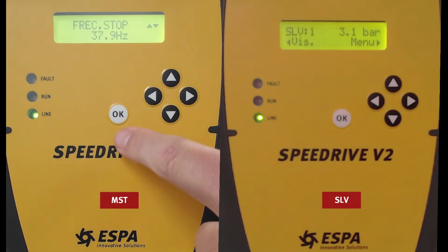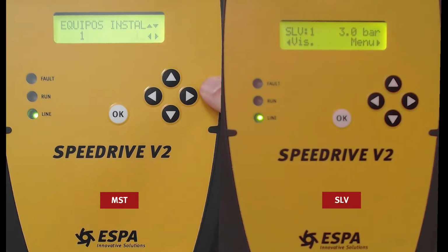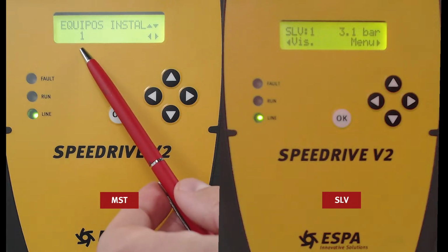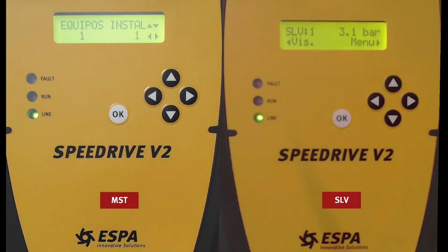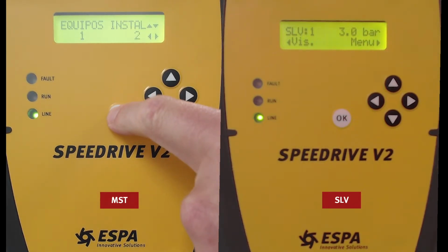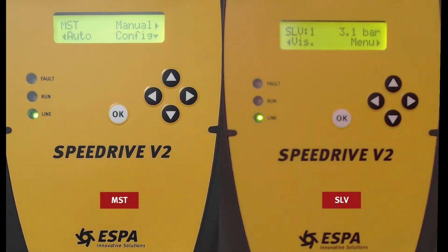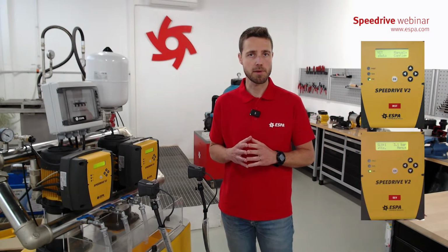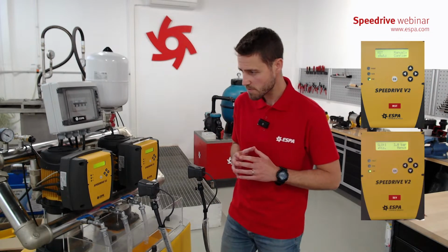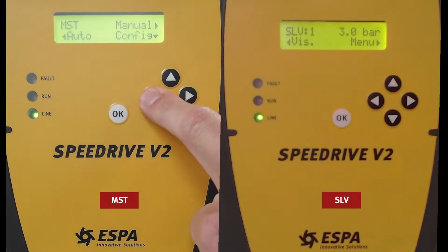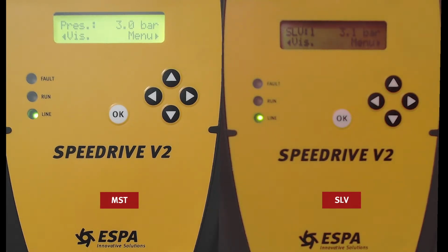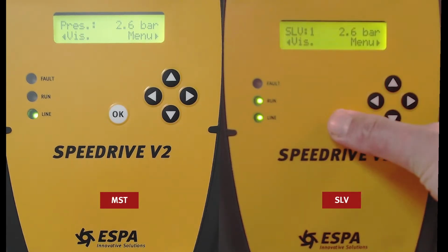Frequency stop, this is calculated automatically. Number of pumps installed, 1. If we leave it at just 1, it will not communicate with other pumps. In this case, it's a 2-pump booster set, so we have to set it to 2 and press OK. And the system automatically saves all the parameters. So you see, with just 3-4 parameters, we can leave the pumps already set up. And now we can go to auto mode again and create a flow. We open the valves, and here again, as you can see, it will maintain the pressure all the time. Open the valves, both pumps.